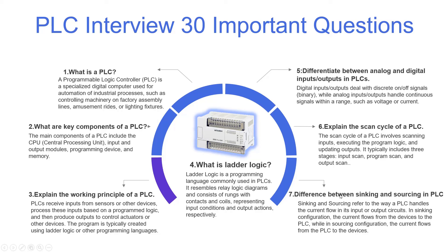What is the difference between sinking and sourcing in PLCs? Sinking and sourcing refer to the way a PLC handles the current flow in its input or output circuits. In a sinking configuration, the current flows from the devices to the PLC, while in a sourcing configuration, the current flows from the PLC to the devices.